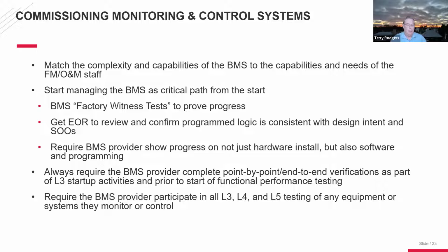Require the BMS provider to participate during the commissioning and startup of anything he's going to be monitoring, whether it's a pump, a chiller, or whatever, so he's present during the functional performance testing in case something doesn't work right. He's there to help resolve issues, and you're also confirming that the piece of equipment is working and is reporting, being managed, monitored, and controlled by the BMS correctly.